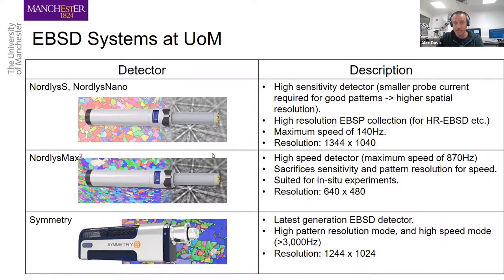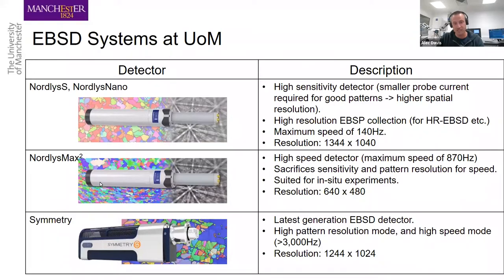We also have the NordlysMax2, a high speed detector that sacrifices sensitivity to collect patterns much more quickly — quite well suited for in situ experiments. Jack and I have run experiments on our Nova system equipped with this camera using an in situ heating stage, collecting patterns quickly as we increase and drop temperature. Its resolution is much lower to achieve that higher speed. Then we move to the new generation of detectors — the Symmetry detectors — which are CMOS rather than CCD. These have very high pattern resolution modes and can achieve speeds over 3000 Hz, with a resolution of 1244 by 1024.